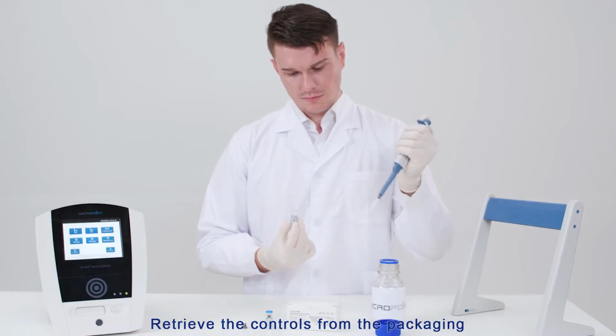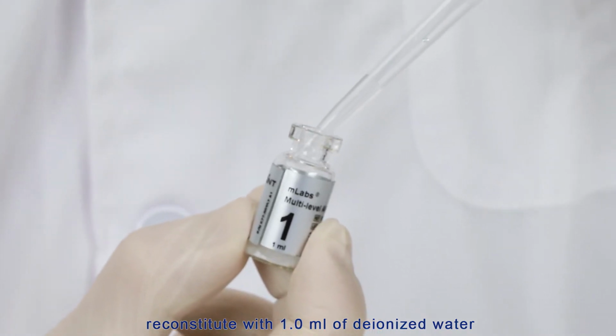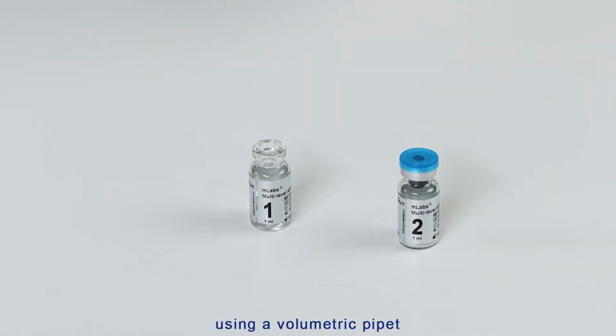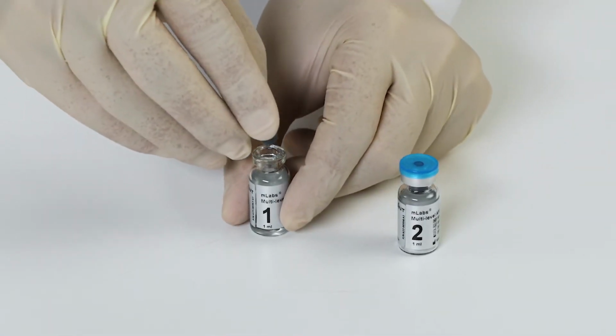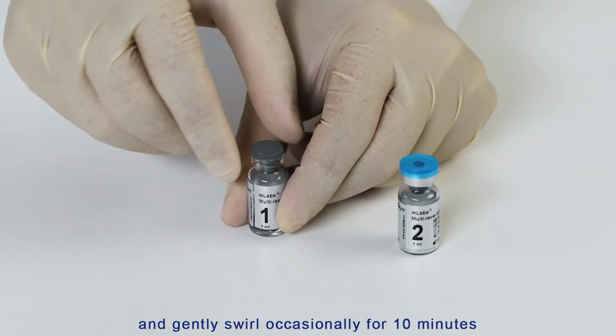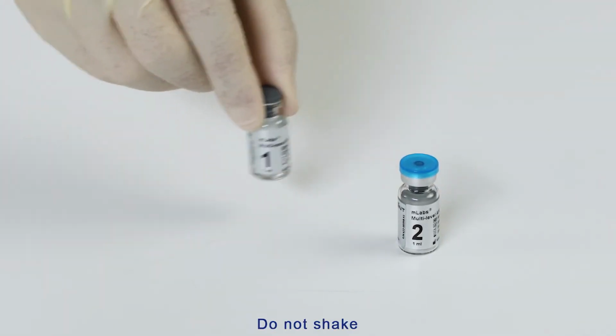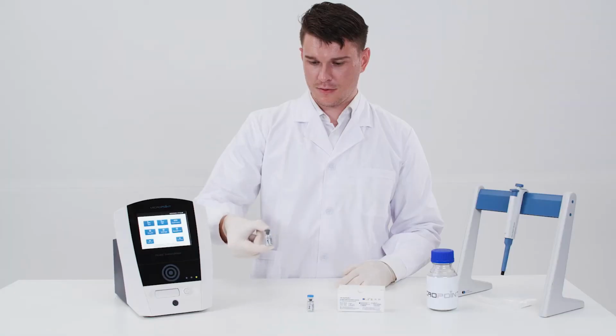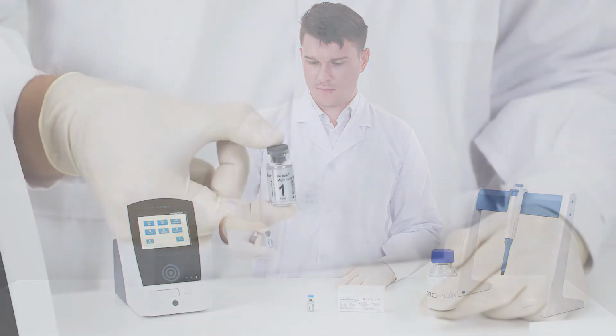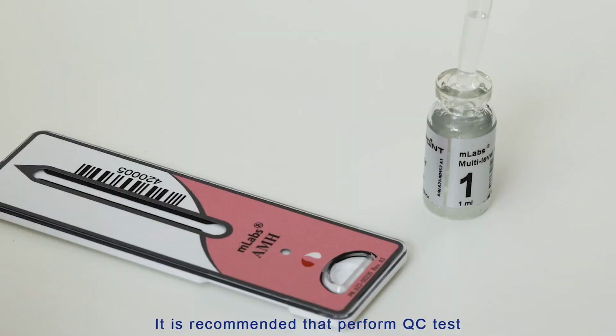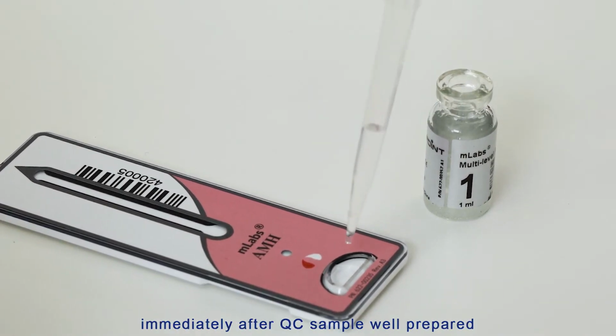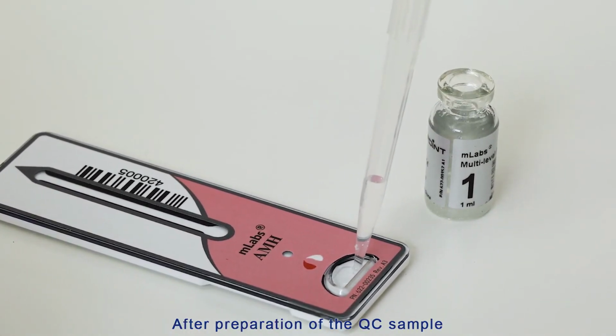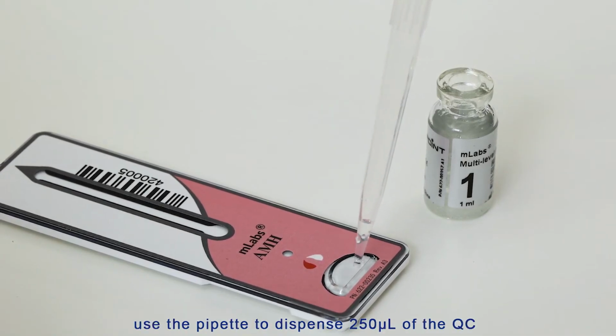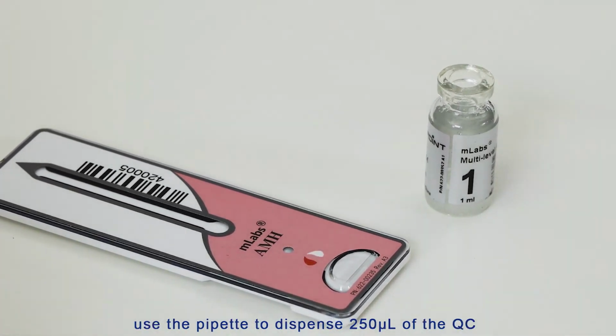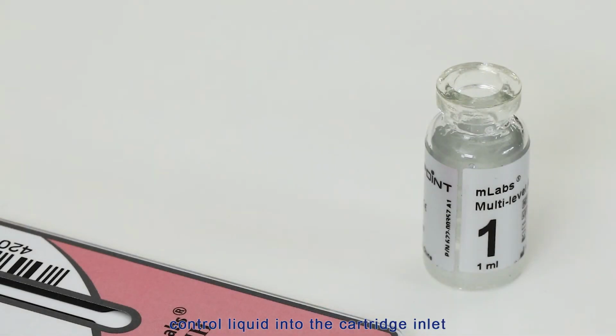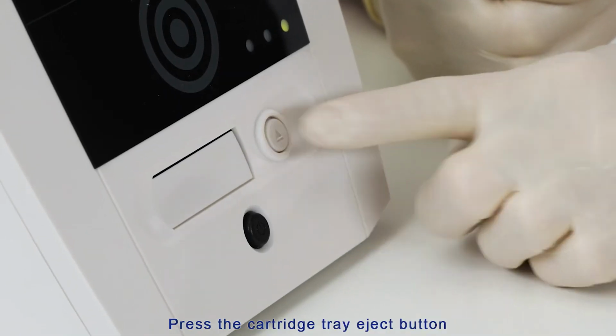Retrieve the controls from the packaging. Reconstitute with 1.0 milliliters of the deionized water using a volumetric pipette. And gently swirl occasionally for 10 minutes. Do not shake. Do not mix mechanically. It is recommended to perform QC test immediately after QC sample is well prepared. After preparation of the QC sample, use the pipette to dispense 250 microliters of the QC control liquid into the cartridge inlet.